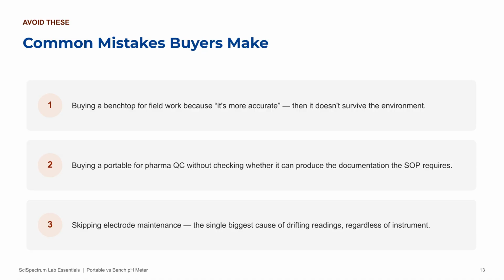Number 1, buying a benchtop for field work because it's more accurate, and then watching it not survive the environment. Number 2, buying a portable for pharma QC without first checking whether it can actually produce the documentation your SOP requires. And number 3, the big one, skipping electrode maintenance. Regardless of which instrument you own, that's the single biggest cause of drifting readings we hear about.